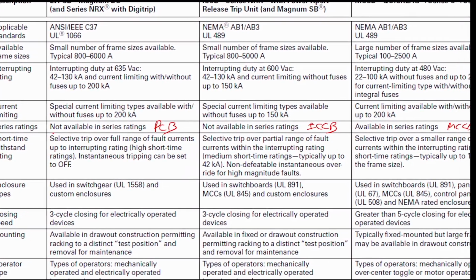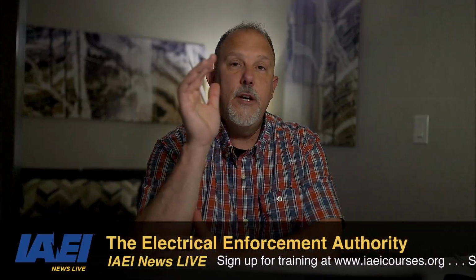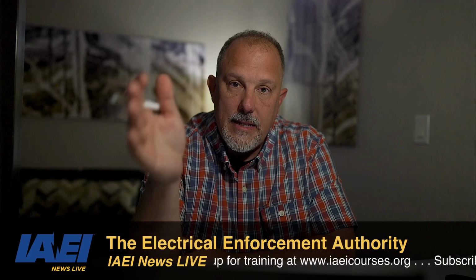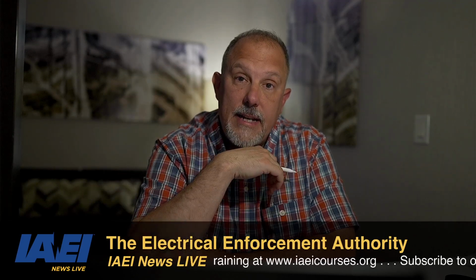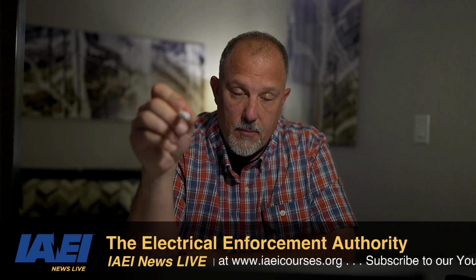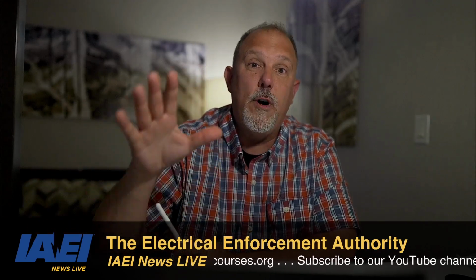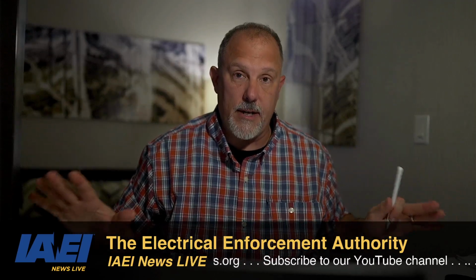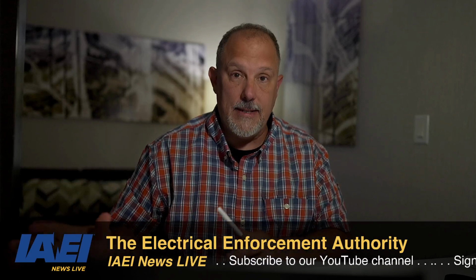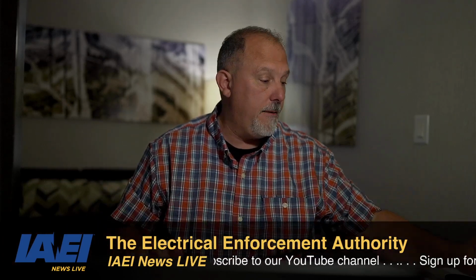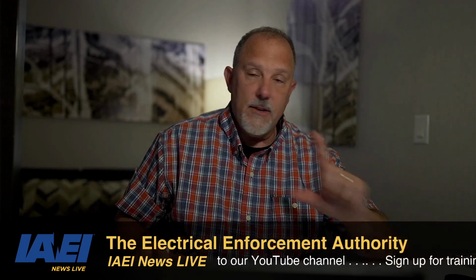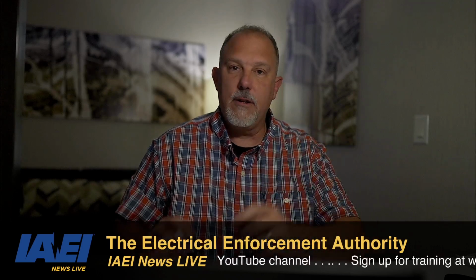What I would say is that the molded case circuit breaker and the insulated case circuit breaker all have an instantaneous pickup. Only certain power circuit breakers, probably a very rare portion of all the power circuit breakers sold out there, will have no instantaneous and just a short time only. So anyway, that little table, you can pause the video and take a look at it and get some things out of it. But it's a really good table. I like the overview that it provides.